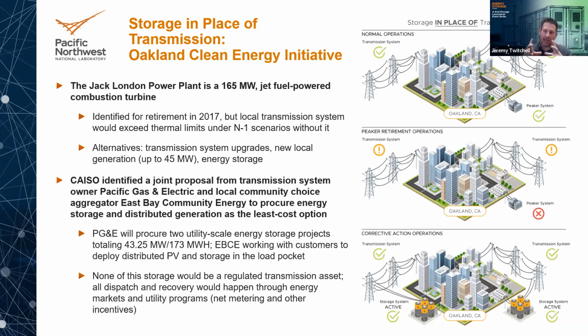The challenge, though, is that without that generation within the load pocket, there were a number of contingency scenarios where Oakland would not be able to be served, where there would be insufficient ability to move power into the load pocket. So they looked at a few options: rebuilding lines, reconducting lines, putting a new natural gas turbine in there. What they found to be the cheapest and most effective option was actually a mix of distributed generation and storage in the Oakland area.